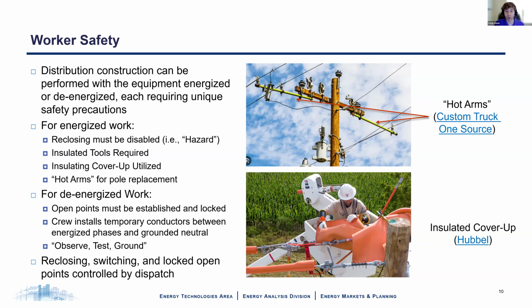The idea is if you have a person who makes electrical contact, you do not want to open and disconnect it and close back in on them. You want it to be like, whoa, I've got to get off. I'm not going to try and reclose. It also trips generally a lot faster. This may be referred to as a hazard or a one-shot mode on the recloser.